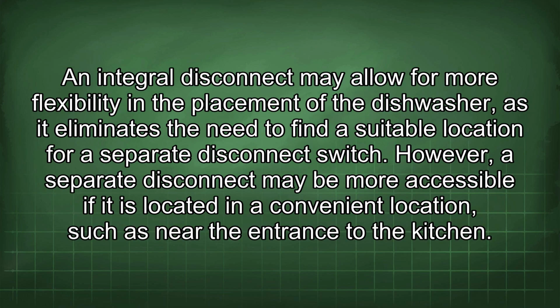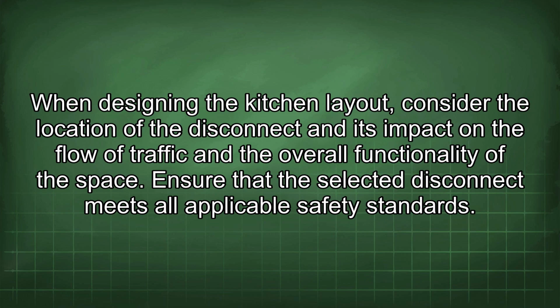Consider the impact of the disconnect location on the overall layout of the kitchen. An integral disconnect may allow for more flexibility in the placement of the dishwasher, as it eliminates the need to find a suitable location for a separate disconnect switch. However, a separate disconnect may be more accessible if it is located in a convenient location, such as near the entrance to the kitchen. When designing the kitchen layout, consider the location of the disconnect and its impact on the flow of traffic and the overall functionality of the space.